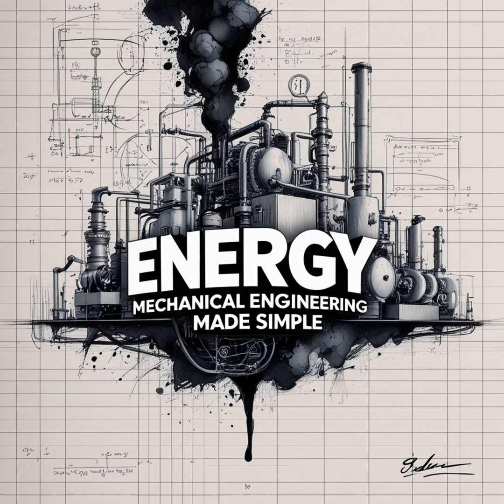But for liquid systems, especially pumps, there's a critical check we absolutely cannot ignore, right? Something about boiling. Yes. Net positive suction head, or NPSH. This is non-negotiable. It's about preventing cavitation. Cavitation? That sounds bad. It is. If the pressure at the pump inlet drops too low, below the liquid's vapor pressure at that temperature, the liquid will locally boil, forming vapor bubbles. Okay, bubbles form. Then what? Then, as those bubbles are swept into the higher pressure regions inside the pump impeller, they collapse violently, implode. And that causes damage. Major damage. It sounds like gravel is going through the pump, it erodes the impeller material, and drastically reduces performance. It can destroy a pump quickly.